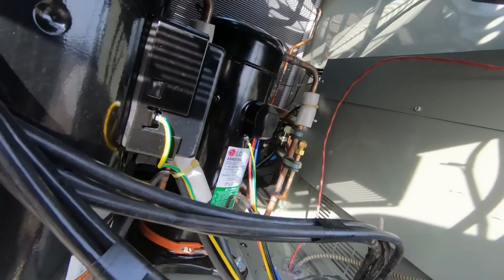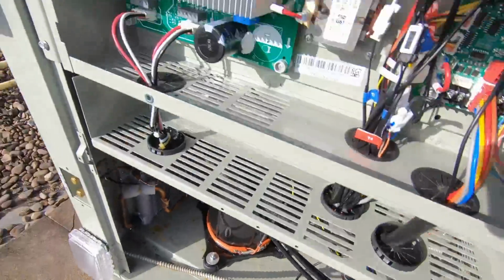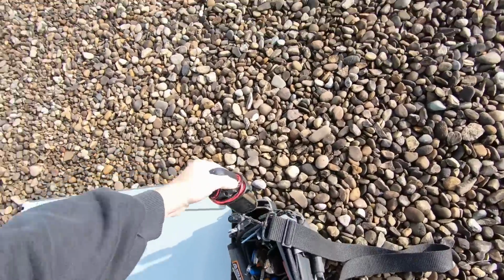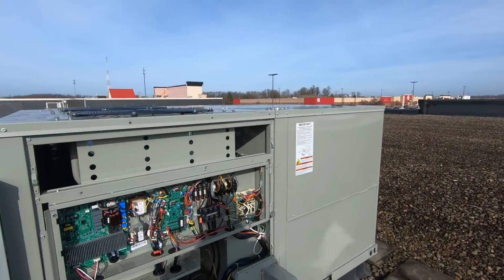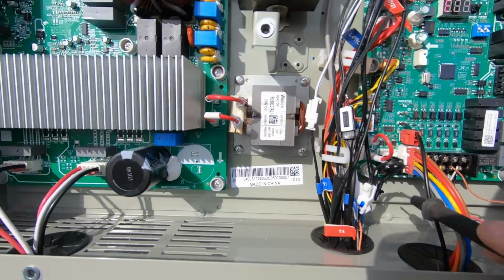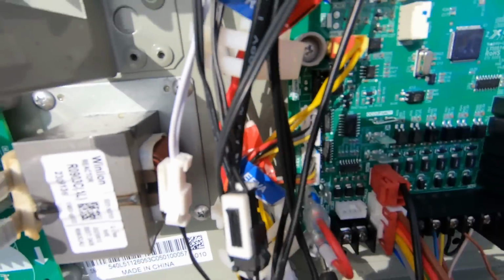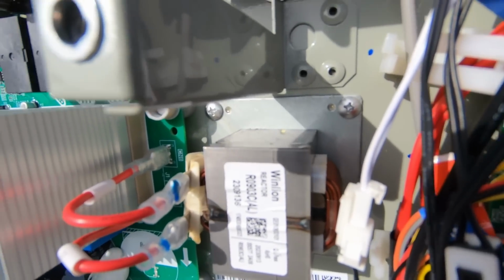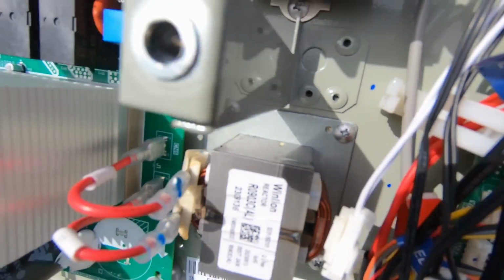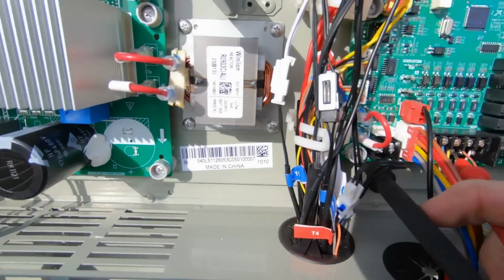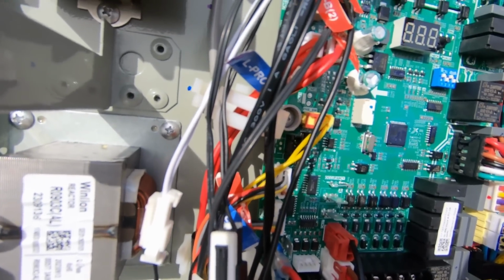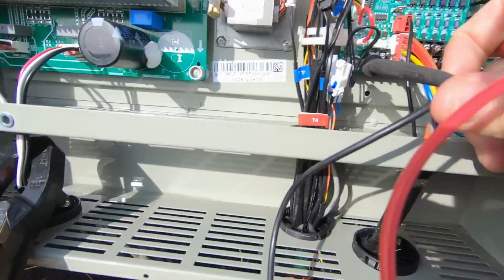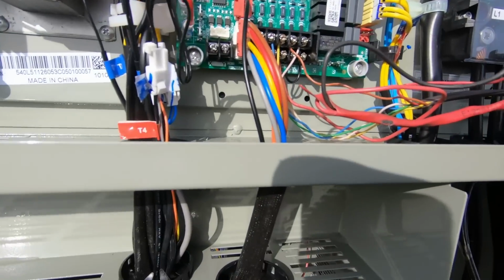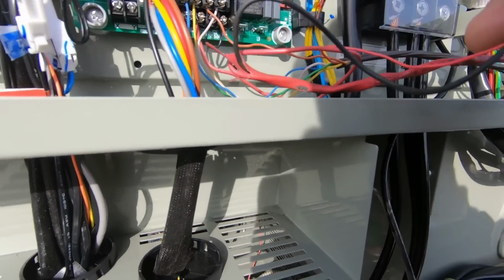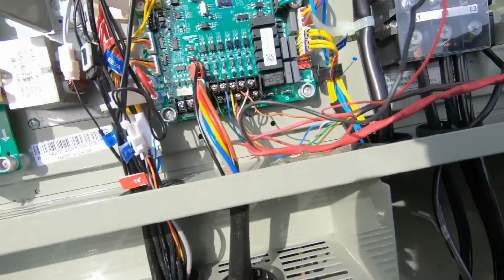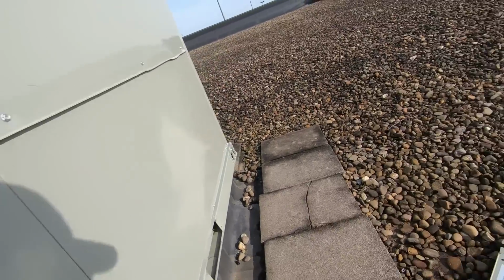A call for what? It is calling for heat at the thermostat. So let's see if we've got a call for heat up here at the unit. All right, so I've got nothing. No 24 volts coming out of the board through the smoke detector. Nothing at W. Nothing. So we're not feeding through the smoke detector. Well, actually, let me check here. Nothing. Yeah, nothing.